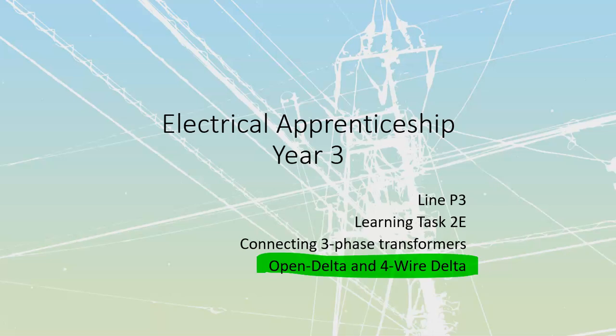And these are going to be your open delta, as well as your 4-wire delta, as well as your open Y, open delta. A couple of things we want to talk about, starting on your page 51, where they start talking about special 4-wire delta connections, is that if we've got a delta connected secondary of a transformer, there's no ground on the system. And if you have no ground on the system, you don't have a neutral on the system, and you have no way to deal with your single-phase loads, lights and receptacles and things like that, that people generally inside of places of business are going to need.